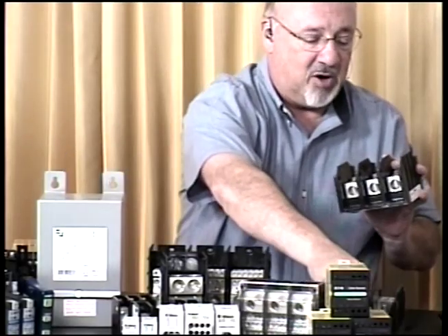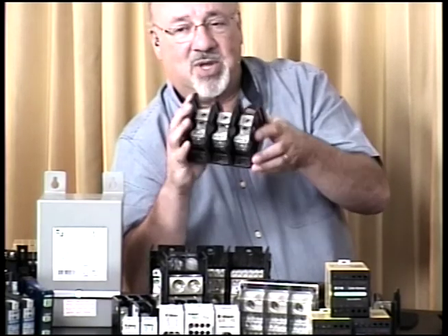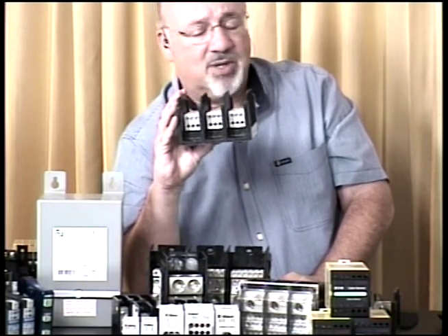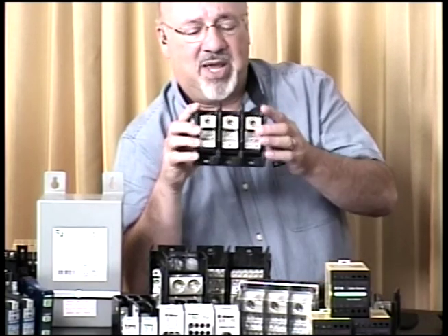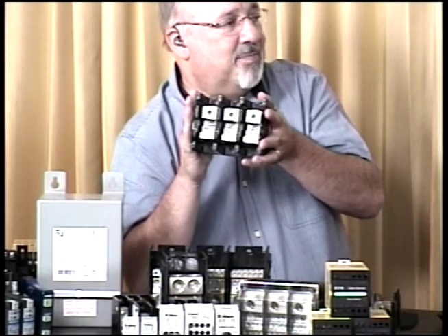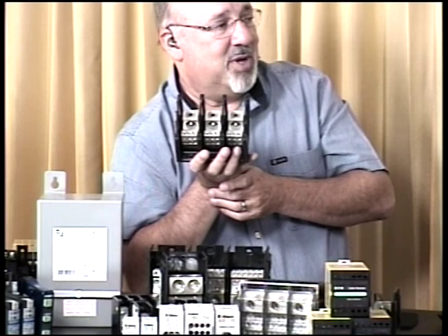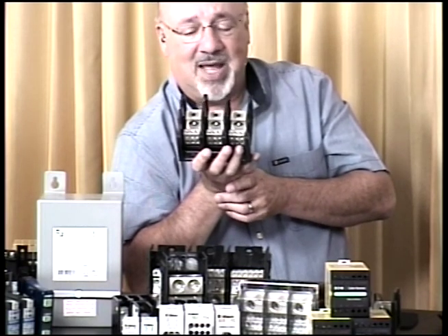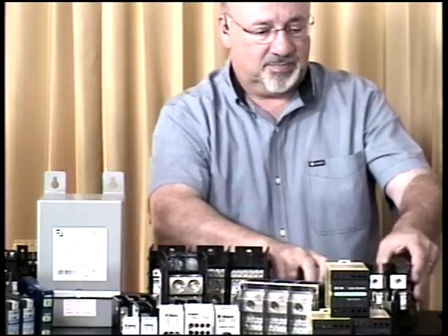Here's the actual power distribution. Again, at the top, your large gauge wire would come into it, and the bottom is where you would branch off with smaller gauge wires to distribute the power to other circuitry within your panel. But this is an open type. It's not finger safe, so if you're going to put it in a panel, make sure you use all the safety interlocks on the panel so somebody that's not authorized doesn't get in there and hurt themselves.